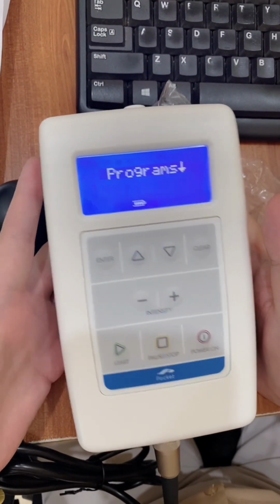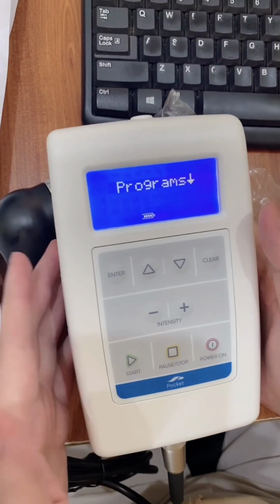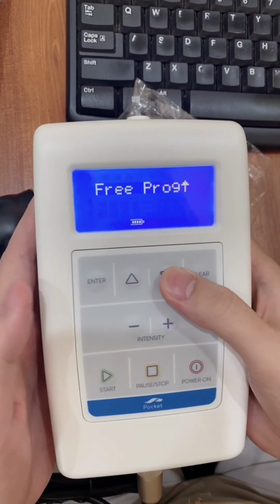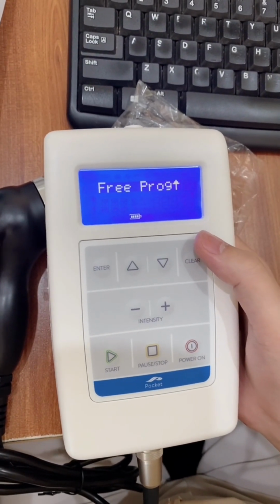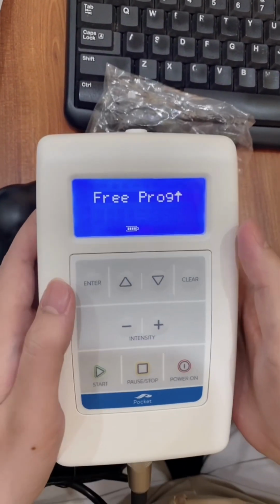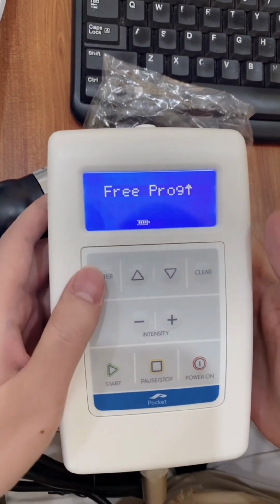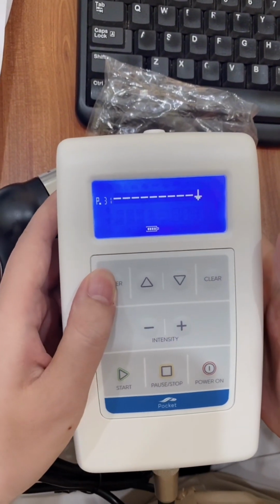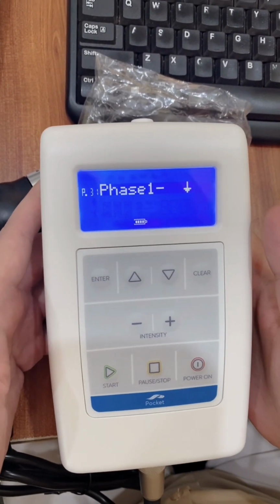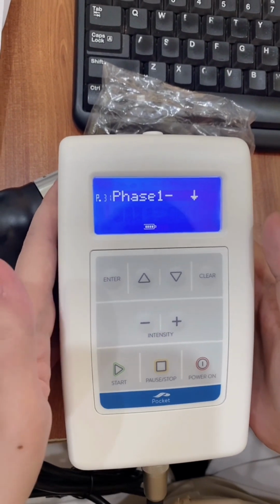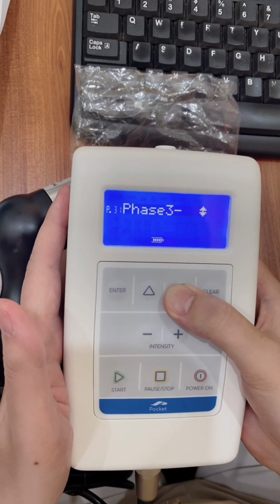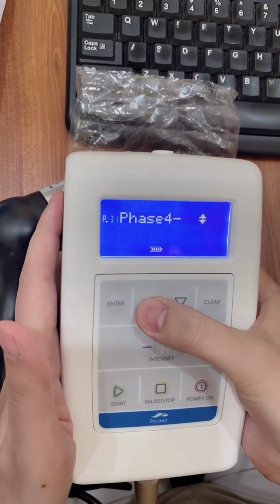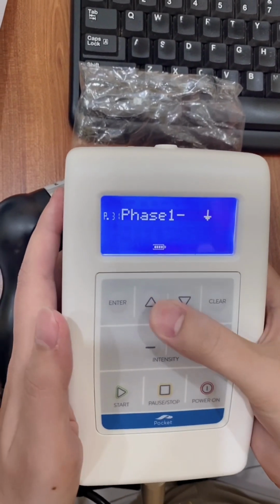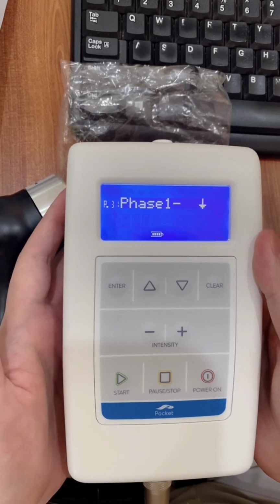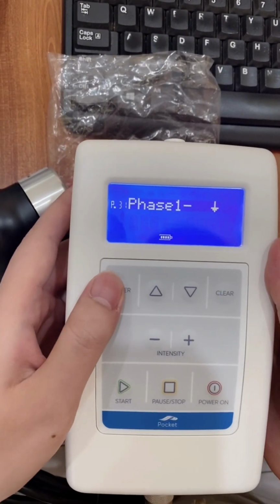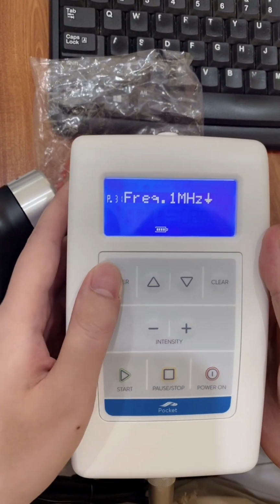And for the best result and effect of the treatment, I advise you to use the protocol where you set up the parameters by yourself. By following each step, press the enter button twice to start setting up the parameters. In a treatment, you can choose to set up to 4 phases, but in my opinion, you just need to use 1 phase for a treatment. And to set up the parameters for the phase, press the enter button another time.